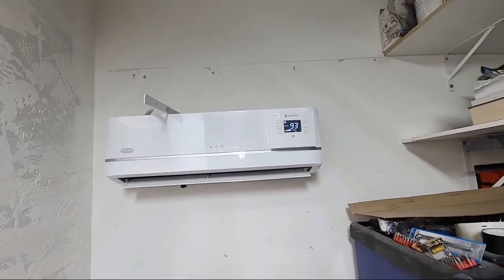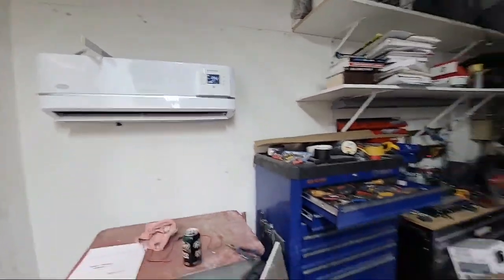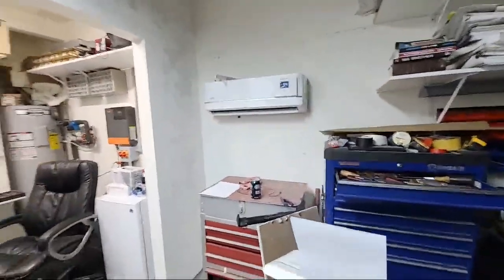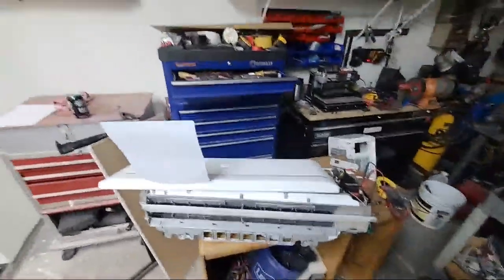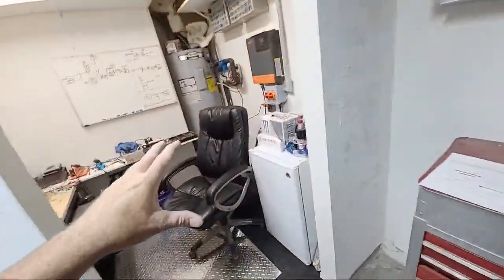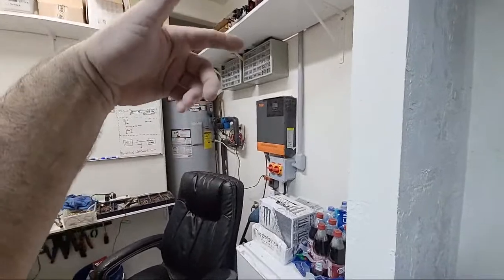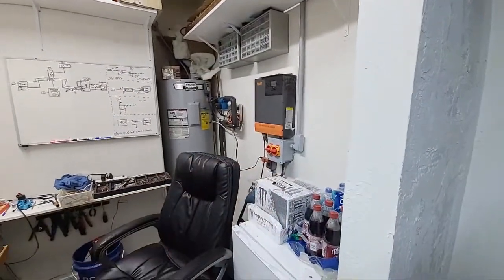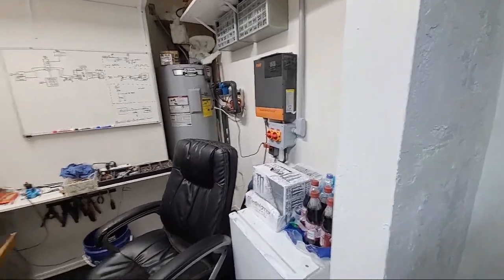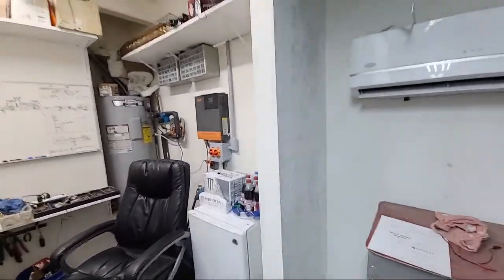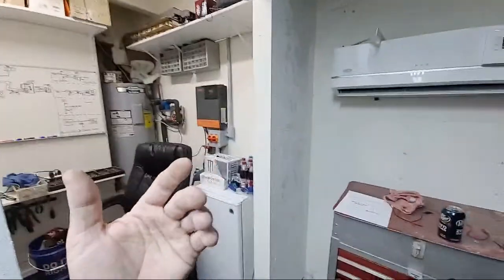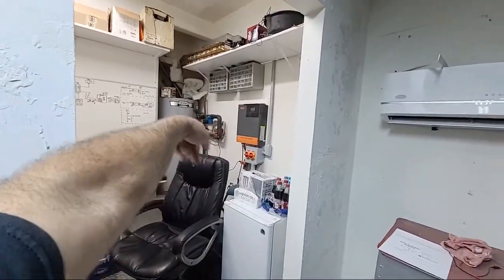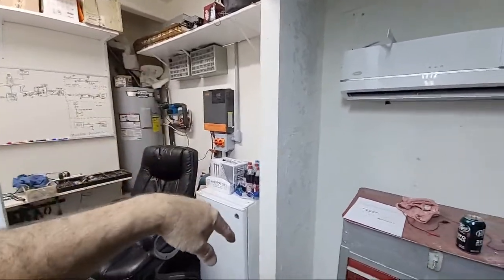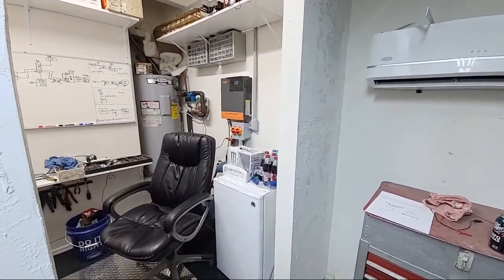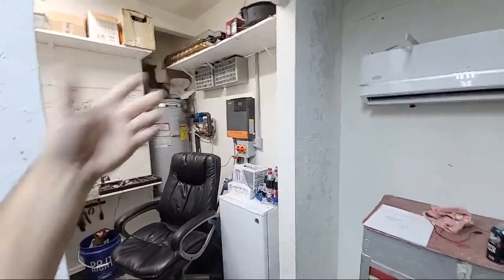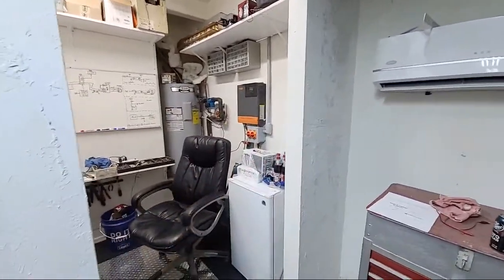The only reason I'm going through this, even though I want AC in there real quick, is the whole idea is to merge my cooling in here with my heat pump I made for my water heater. It's outside, put it all in a new cabinet out there. Split the coil because it's big enough to use half for a condenser and half for an evaporator, and I'll series the discharge through the heat exchanger with the pump water, then through the coil. Basically, if the water heater is getting too hot, I'll have it stop the water pump and turn on the outdoor fan.